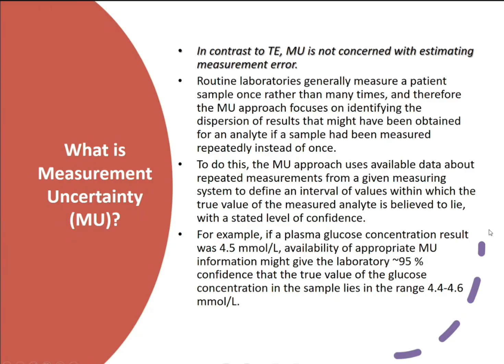Right. Then you come to measurement uncertainty. This is something which NABL has asked most of the NABL accredited labs to do. Basically, it quantifies the range within which the true value lies, and it is required mainly for quantitative results. It gives you an idea whether the variation that you're observing in values is within acceptable range or not. Mathematically, you can calculate it as it is proportional to the percent CV, and most labs use 1.96 or 2 multiplied by percent CV, and that is what MU is, right?